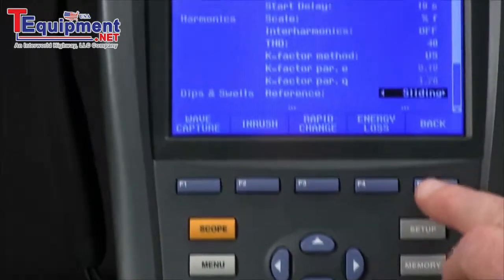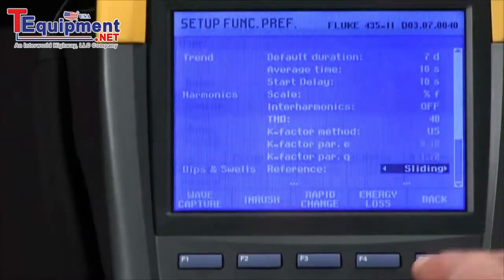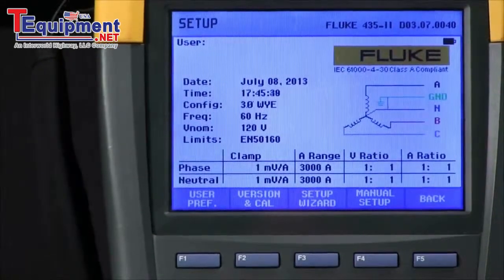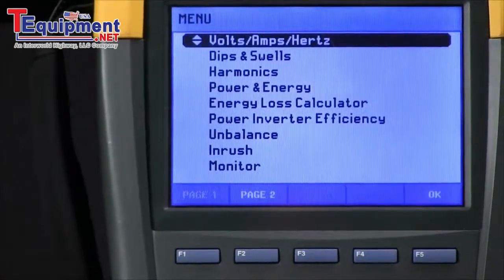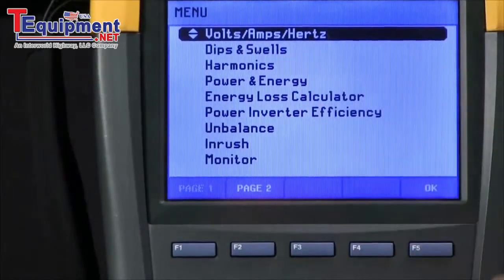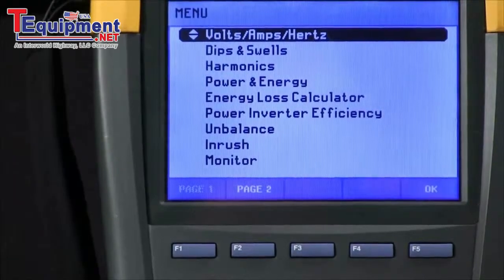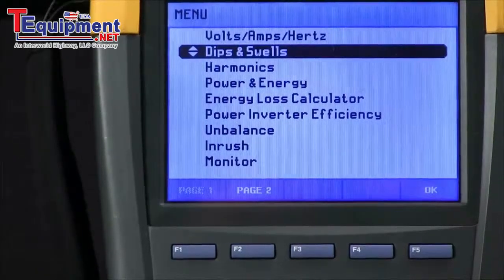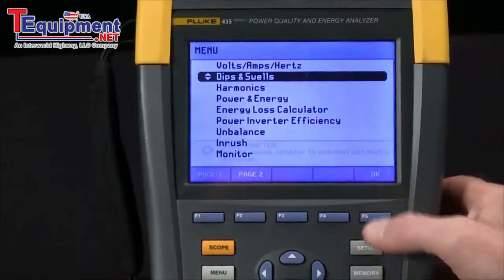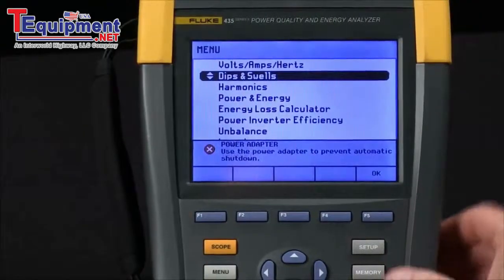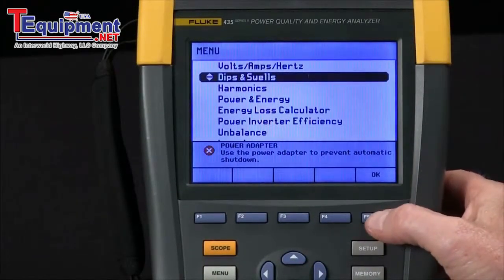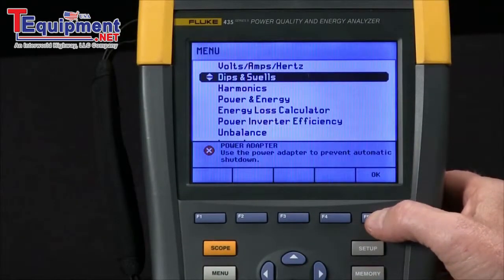Sliding will take that measured voltage as the reference and use that for all event capture. Once we've done that, we hit the back key and come to our menu. We want to select dips and swells with the arrow key, then F5 for OK. Use a power adapter if you want to run a long-term test.